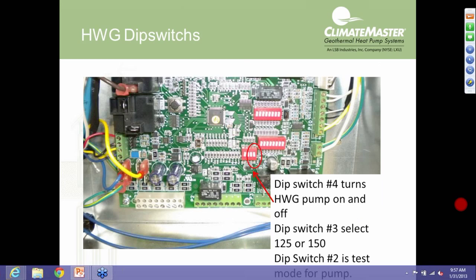Back to our dip switches, bank 3. The remaining 3 dip switches, again, we just talked about dip switch 1, but the remaining dip switches are functions for the hot water generator. Number 4 turns the pump on and off. Number 3 allows you to select between a cutoff point of 125 degrees or up to 150. If you do 150, though, you better have an anti-scald valve installed in the system.